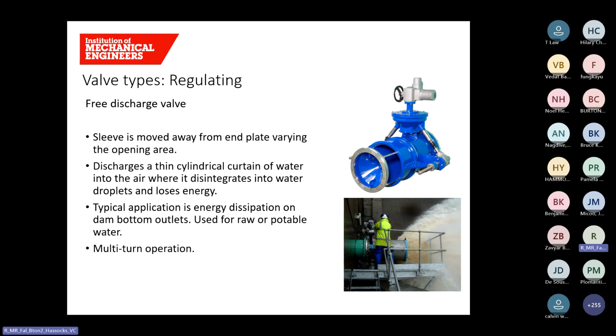Similar to the piston or plunger valves, free discharge valves are used in end-of-line applications, particularly where there's a high dissipation of energy required. They operate by moving a sleeve closer or further away from an end plate, allowing more or less flow to pass through, hence regulation. The water discharges in a thin cylindrical curtain into the air, and it disintegrates into droplets and loses its energy. Not all of the energy is lost though, so cavitation is less likely to occur. These valves tend to be used at the bottom of dams where there's high pressure and energy dissipation is required. They're multi-turn operation and they provide drop-tight performance.